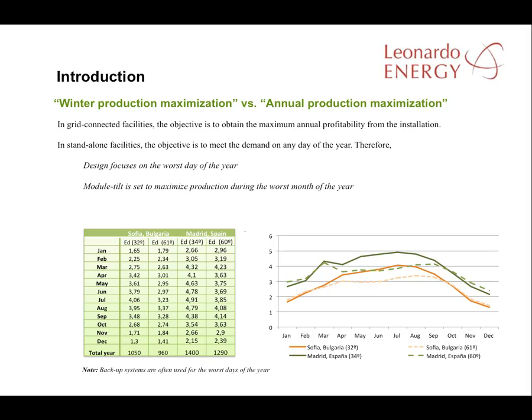It may be advisable to add additional generation capacity, such as a backup diesel generator, but even so, consumption needs on the worst day of the year is still the basic measure. In the table on this slide, you can see the worst month of the year in Madrid would be December, with a production of 2.15 kilowatt hours per day. But production can be optimized during this month to get 2.4 kilowatt hours per day. This option will need to be considered, even if it means an oversupply over most of the year.